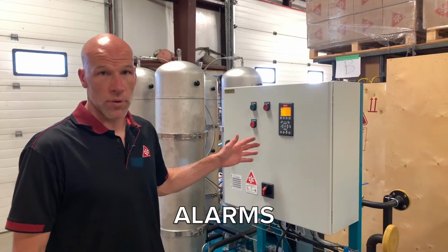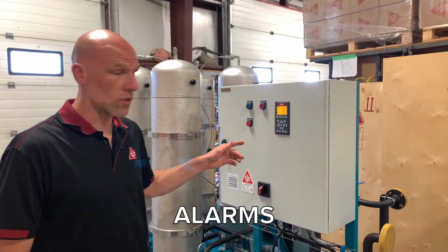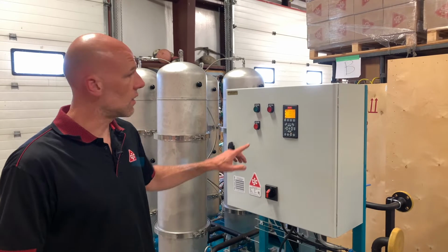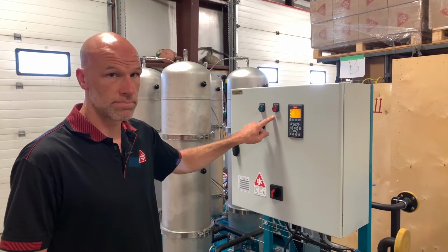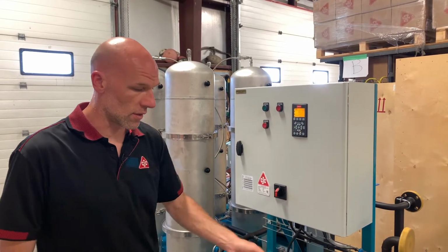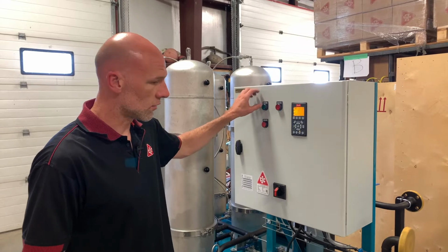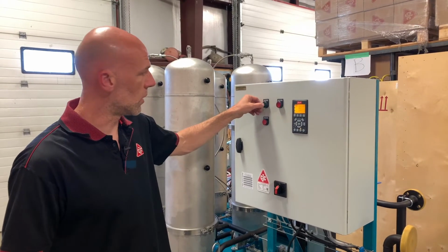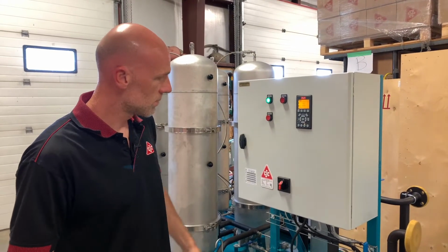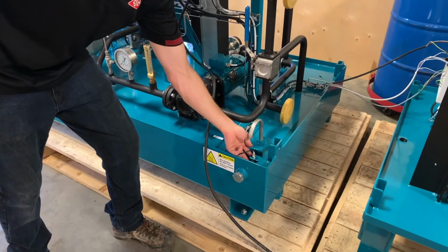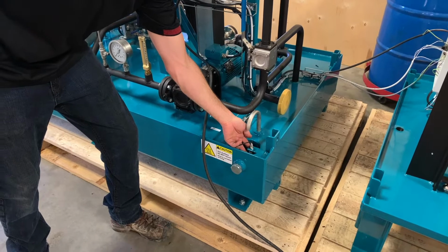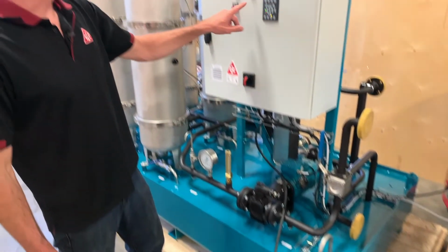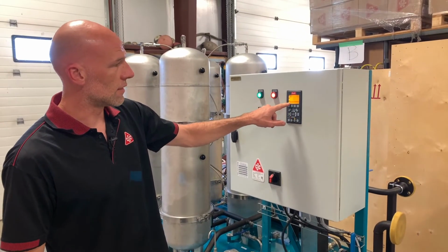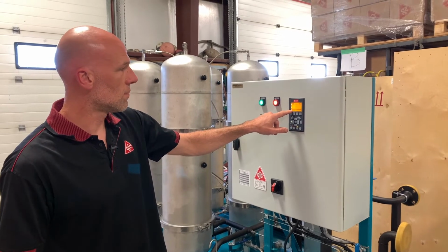While the unit is operating, if there's a safety trip situation, it will shut off the unit and light the alarm button. So I'm going to demonstrate just using the spill switch, and you'll see the light come on and the unit will quit. So you can see the light has come on, it says leak detection on the display, and the unit has stopped.